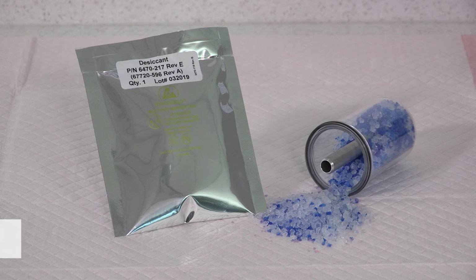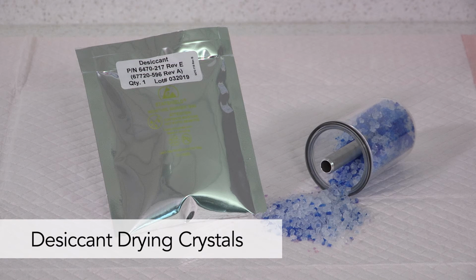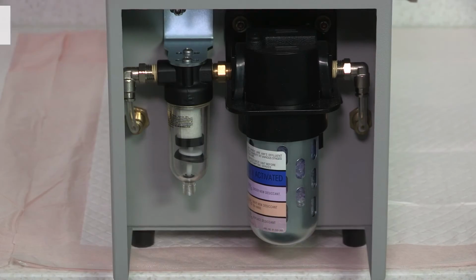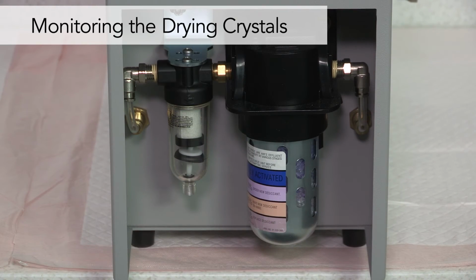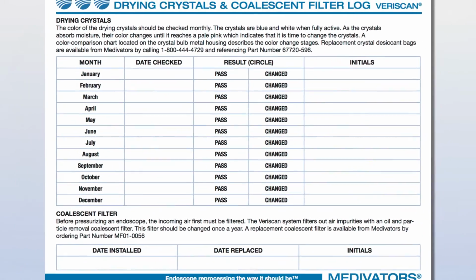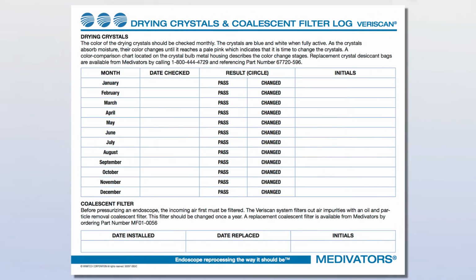The desiccant drying crystals must be installed before leak testing an endoscope, as they ensure that only dry air is used during leak testing. Monitor the condition of the drying crystals on a monthly basis and record the results on the drying crystals and coalescent filter log.